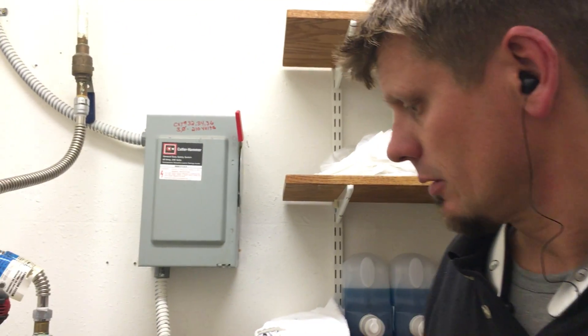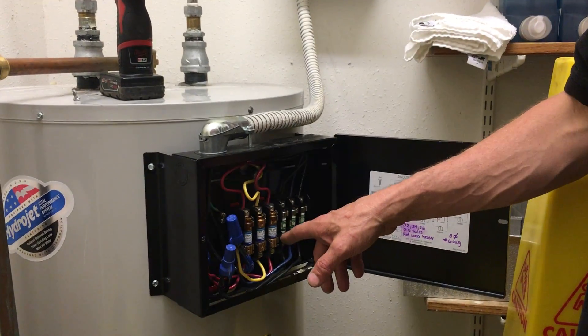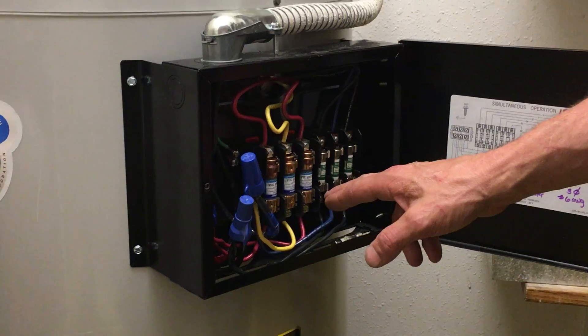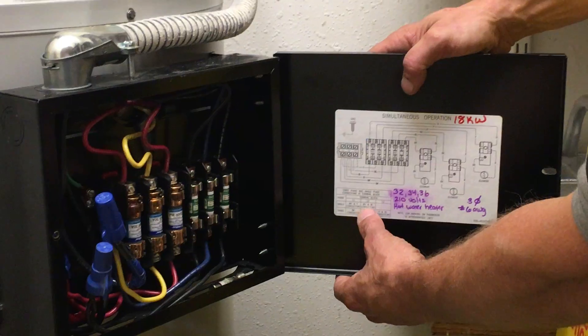This is Joshua Peterson here at Peterson Electric. I want to talk to you today about a hot water heater. The fuse burnt up right here, and that was a concern — it was on this leg. This was originally wired at a single-phase option.